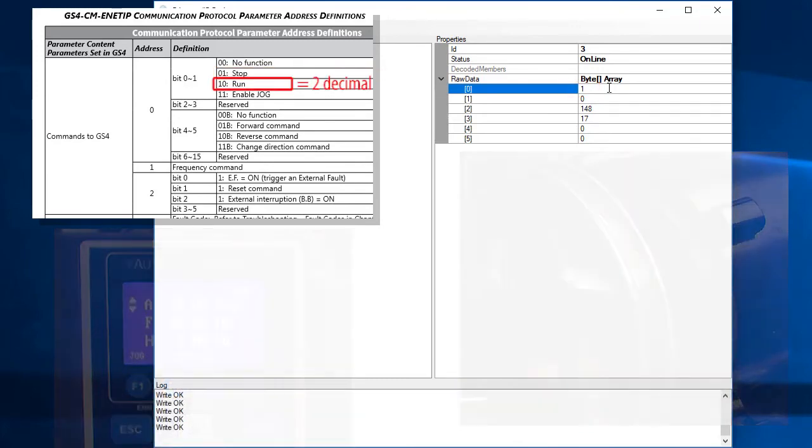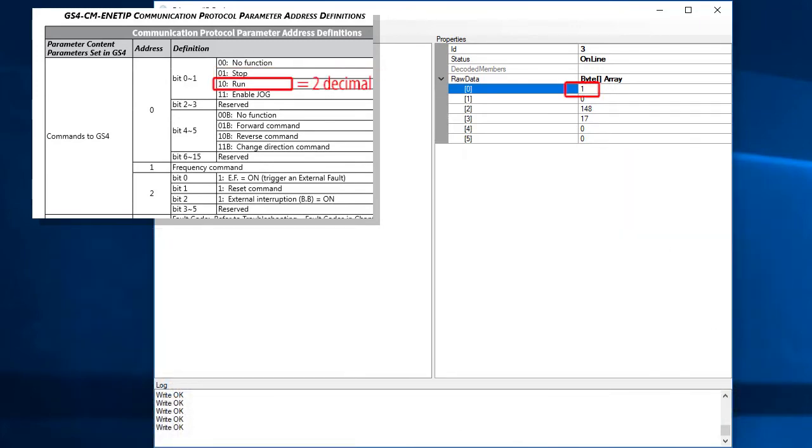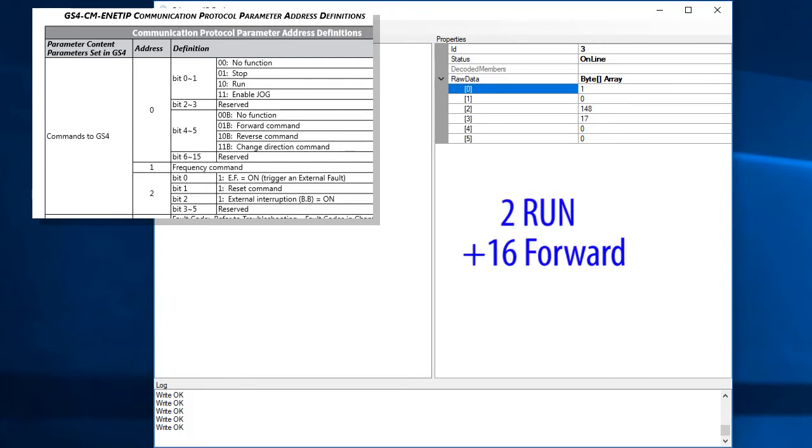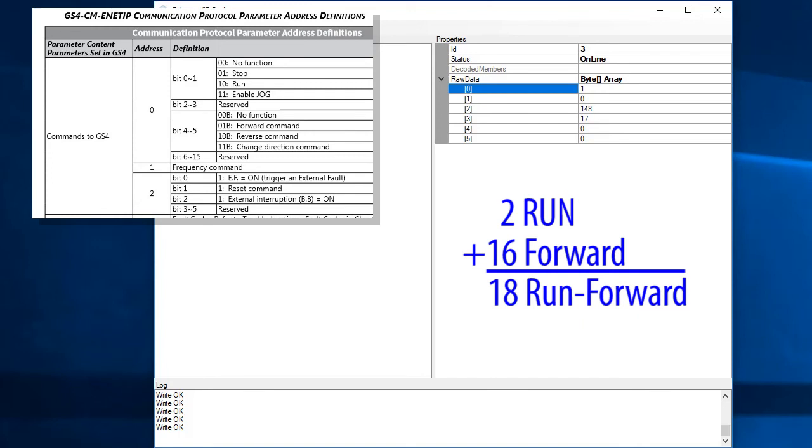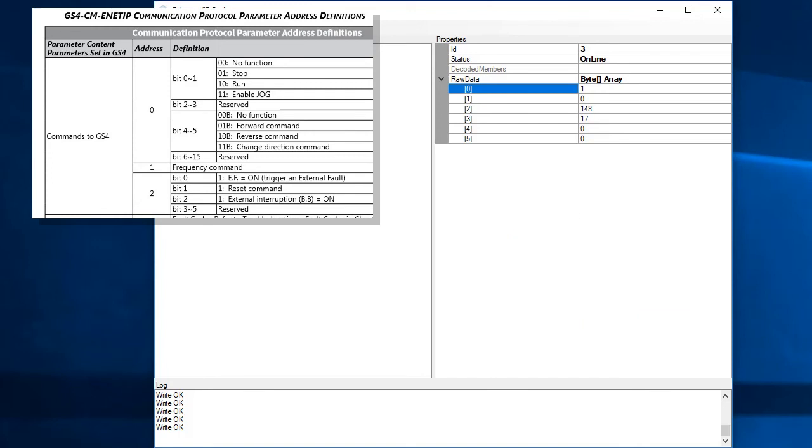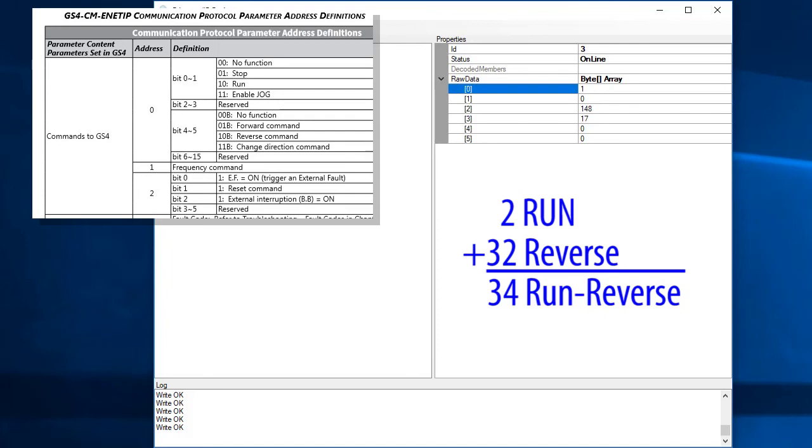Now, would you normally enter a 2 to get the drive running like I did here? Well, no, because you don't know which direction the motor is going to rotate. It's much better to say I want the drive to run and go in the forward direction so we would enter an 18 here instead of a 2. Or, to run in reverse, we would enter a 34.